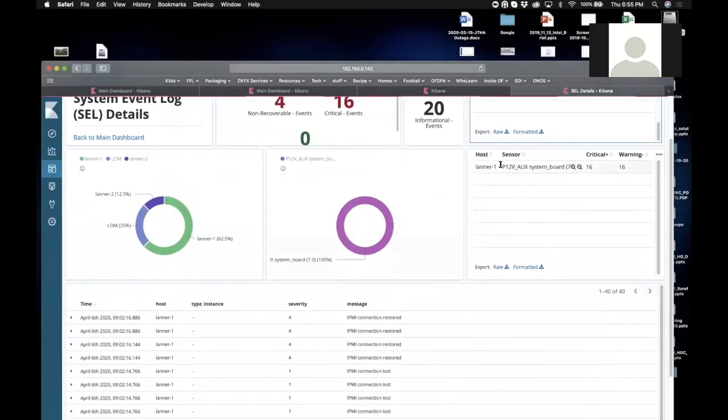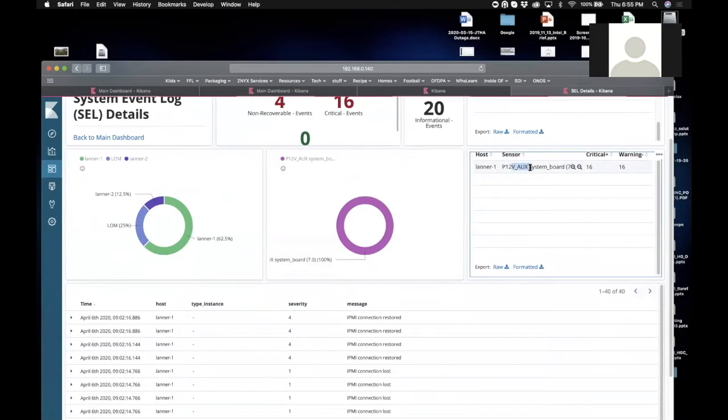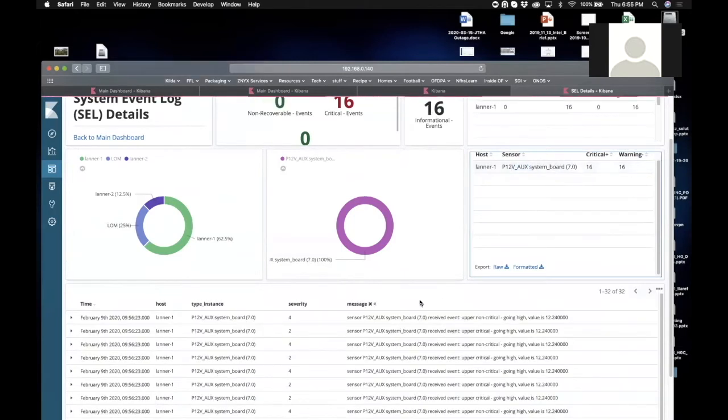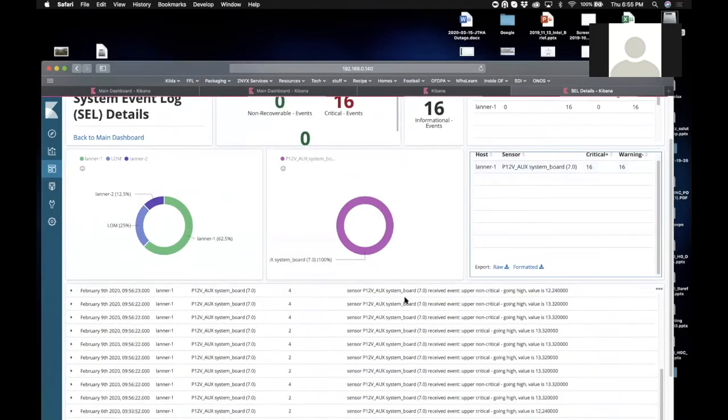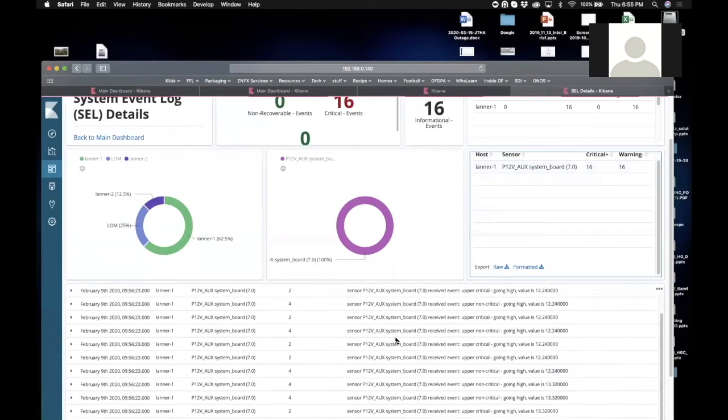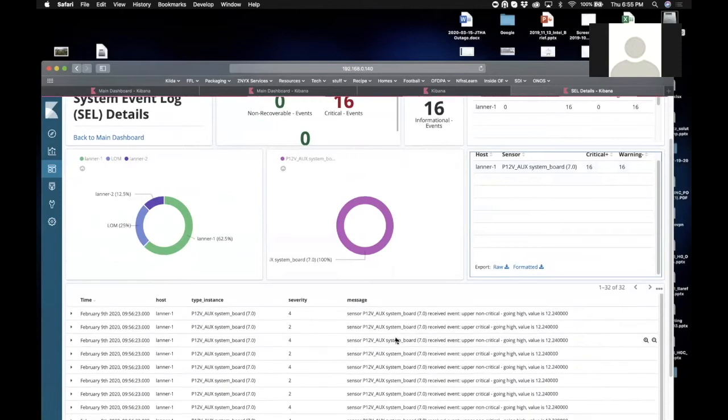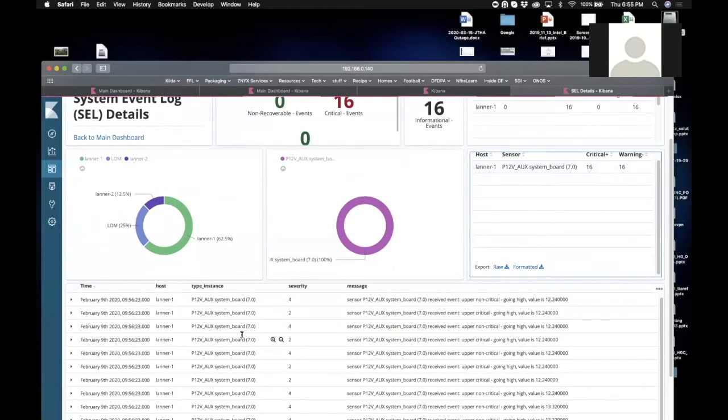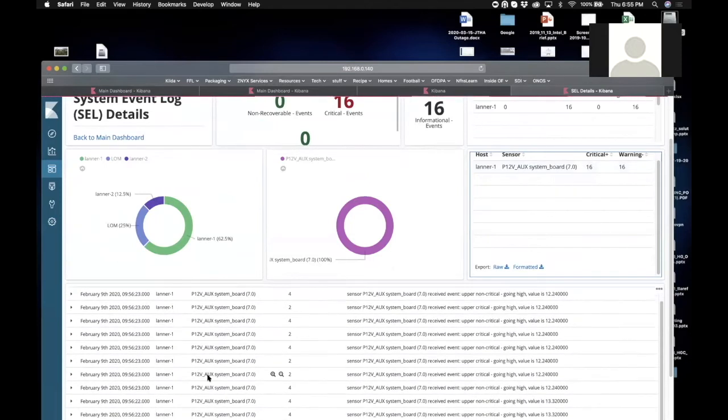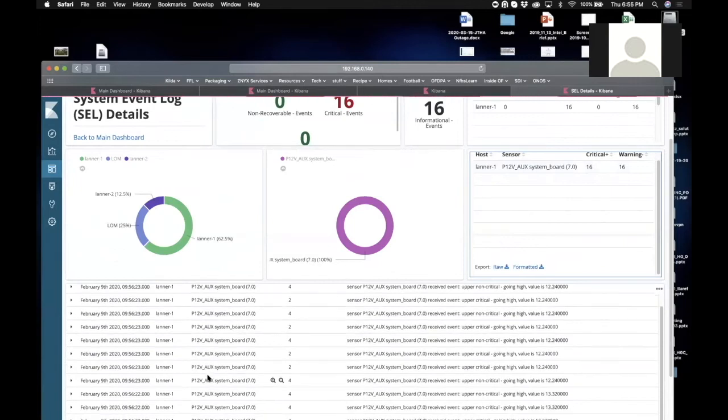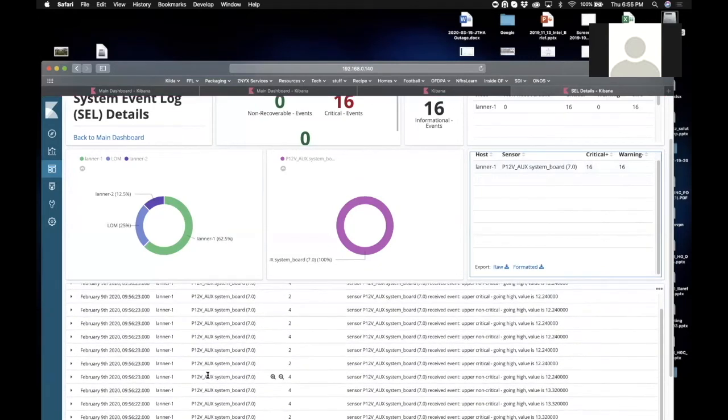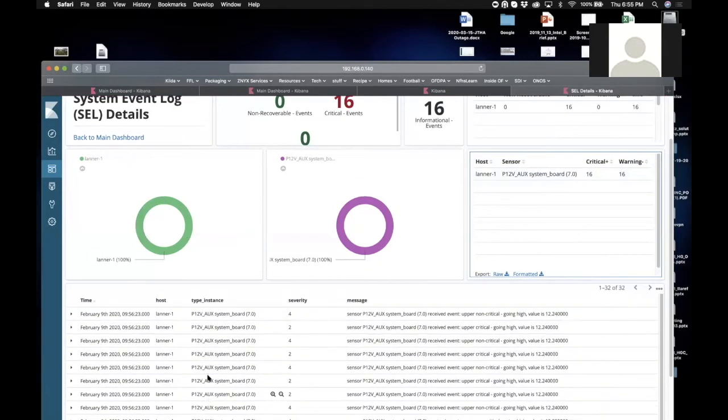Okay, so we see that it's the 12 volt rail is generating events and we see that we get the error messages from the syslog for that 12 volt event. And you see that this event lasted for about one second, less than one second, it crossed through thresholds.